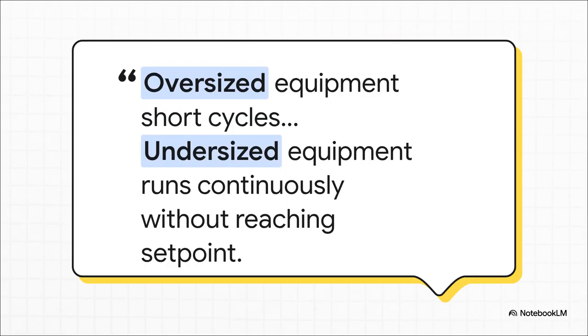Getting this calculation right is critical. As the source material says, oversized equipment short cycles and fails to dehumidify properly, while undersized equipment runs continuously without reaching the set point. In other words, if you get the size wrong, you've just spent thousands of dollars on a system that will never keep you comfortable and is basically doomed to fail early.